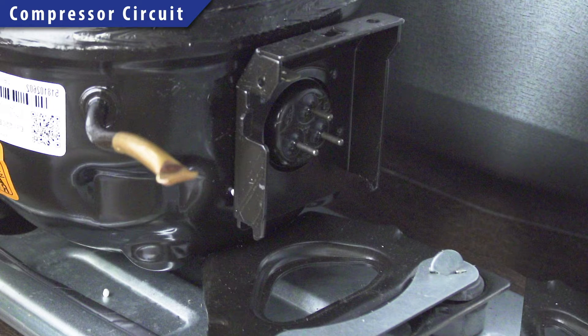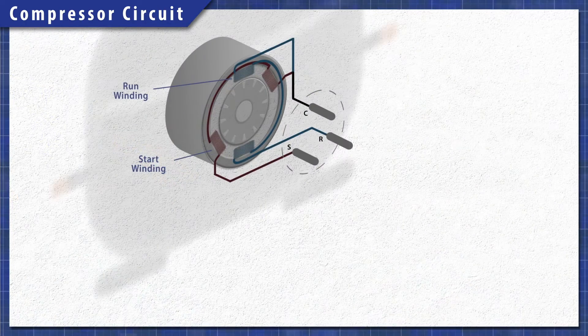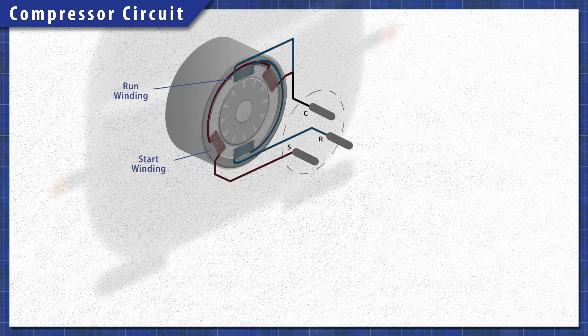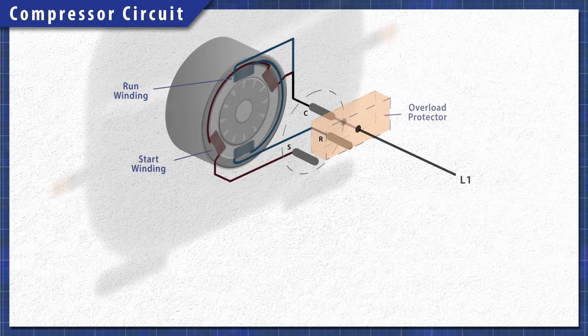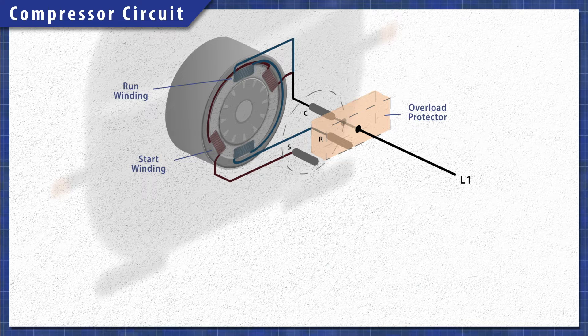The compressor uses a single phase motor. It has a start winding and a run winding which are both connected to a common terminal. Attached is an overload protector that disconnects power if the current or temperature gets too high.